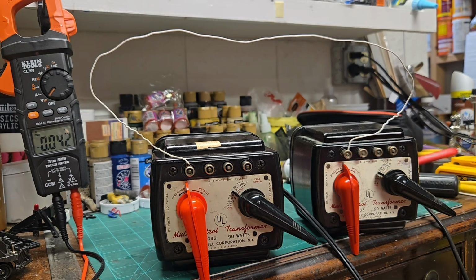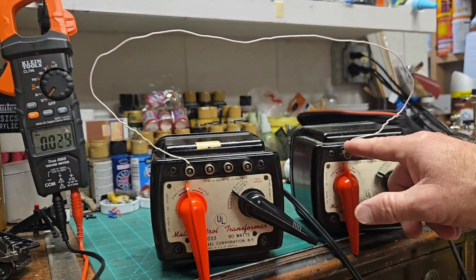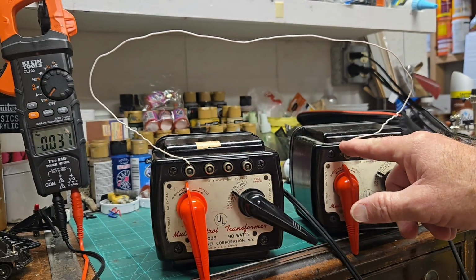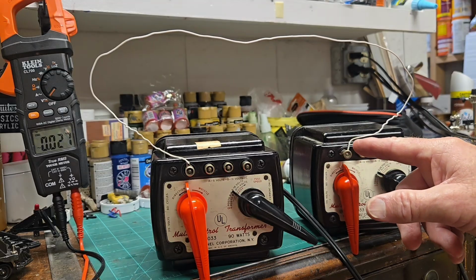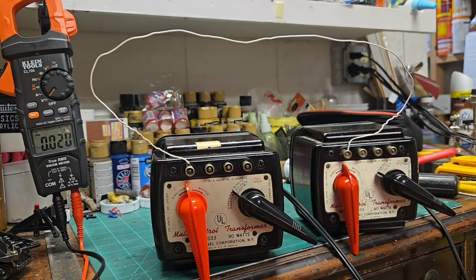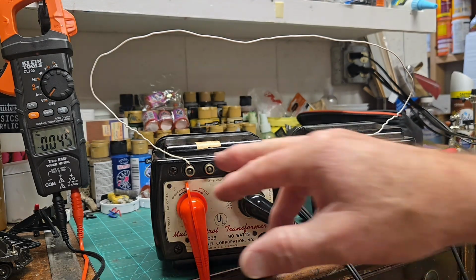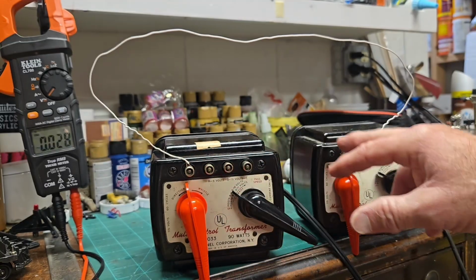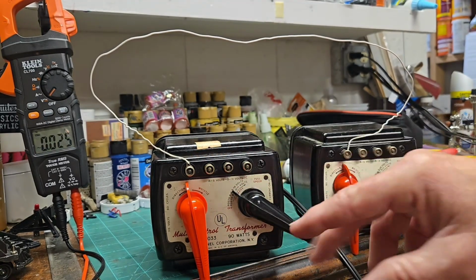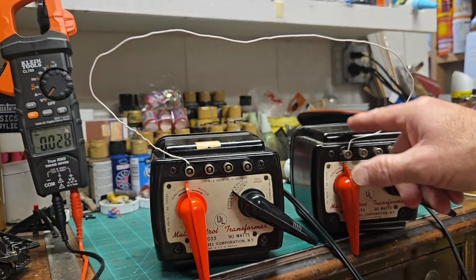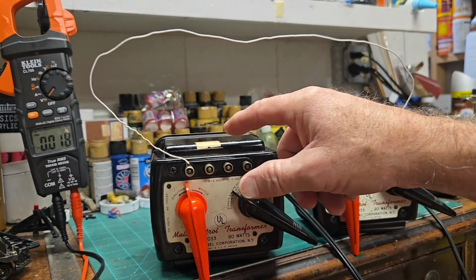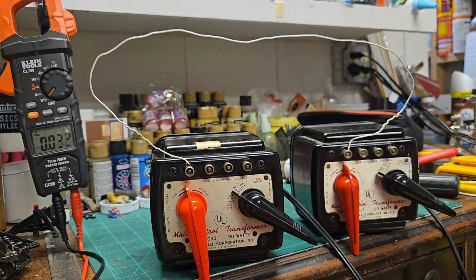So I'm going to test this real quick. Both transformers are plugged in and working. I've got the U posts on both transformers. I have no clue which is which, but you have to start somewhere - it's a 50-50 chance, so these could be in phase or not, we just don't know. But you need to start somewhere, so tie your two posts that are the same, like both A's or both U's - just interconnect the same corresponding post on both transformers.